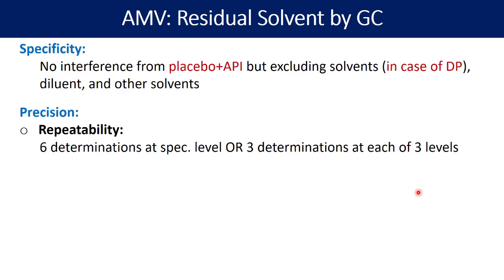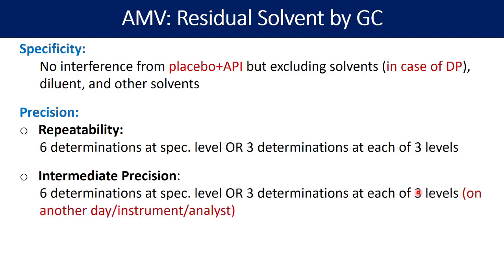This is the first level of precision — repeatability. The second level is called intermediate precision. You determine repeatability on one day, then on another day using another instrument, and you ask another analyst to perform the similar repeatability experiment. If the results are also precise and meet the acceptance criteria, that experiment is called intermediate precision — performed on another day, using another instrument, by another analyst.